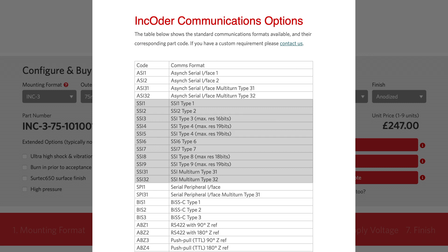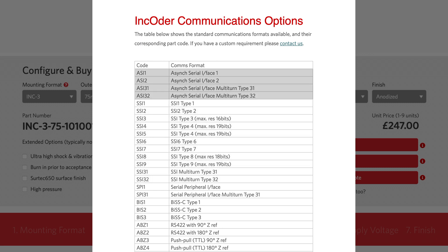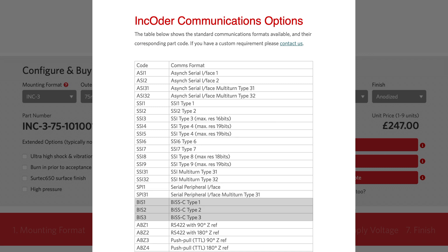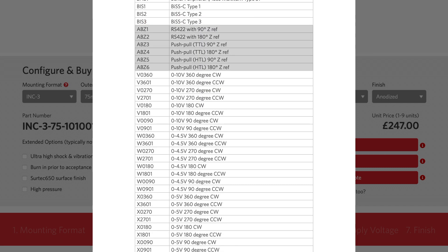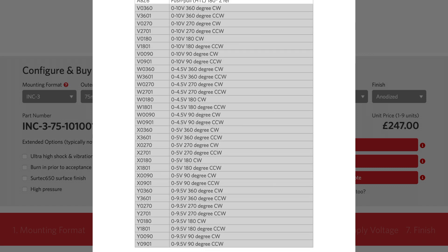Refer to the encoder product guide for additional detail. ASI is similar to SSI but there's no synchronisation clock signal. SPI is serial peripheral interface and is widely used between encoders and microcontrollers. BiSS-C is very similar to SSI and is popular in the latest generation of motor controllers. AB pulses is mostly used for incremental encoders and motor drives.